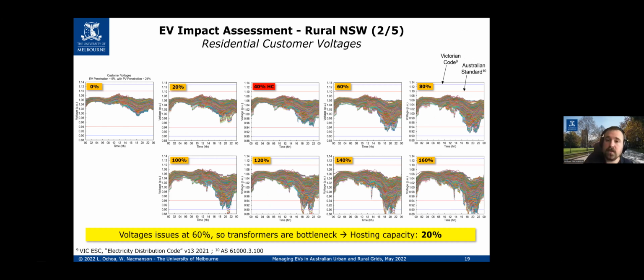So if we move on to the next slide, we can now see that we're looking at the residential customer voltages for the same feeder. Now here the voltages perform better than, say, the asset utilization for the LV transformer. And if we purely look at voltages, we can go up to 40% before we start getting some issues for some customers, not all customers. However, if you had to pick, okay, what's the hosting capacity for this HV feeder, you're first going to be limited by those transformers, which need to be solved before you then move on to the next problem. So despite issues at 60%, the hosting capacity is still 20% because we're limited by some problematic assets. Those problematic assets need to be resolved for those problems to be resolved, essentially.